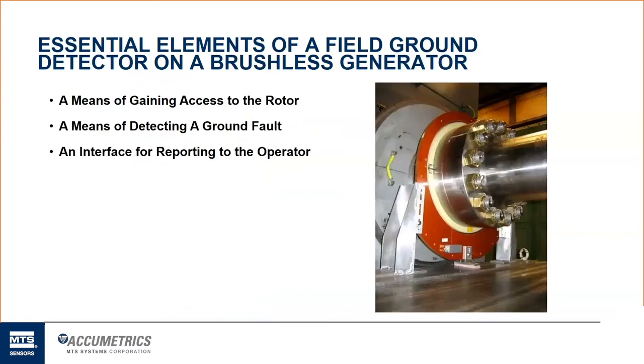So what are the essential elements of a field ground detector on a brushless generator? It's a means of gaining access to the rotor, like I mentioned before. How do you get access to something that's rotating and spinning at 3,600 RPM on a giant piece of machinery the size of your house? It's a means of detecting a ground fault that may occur within those field windings out on the generator itself. And then it's how you report that information or interface with the customer, with the operator. What type of data are they going to receive?